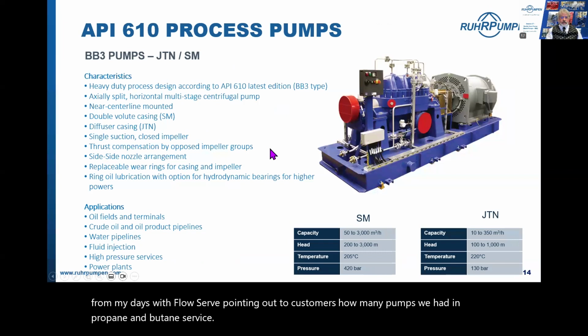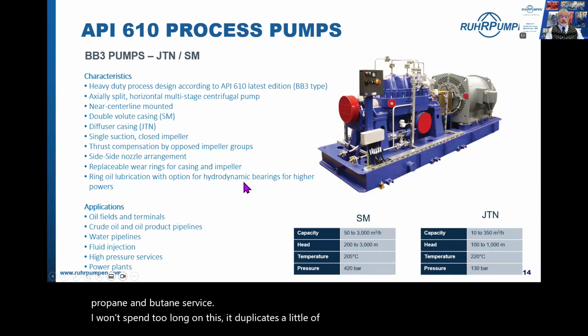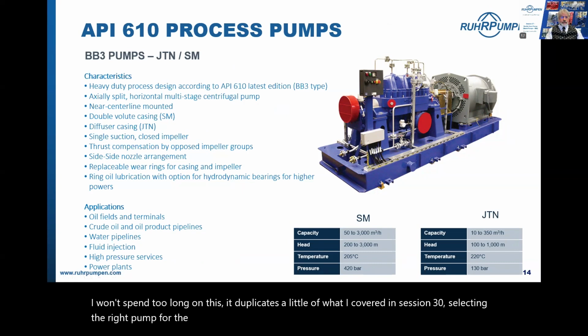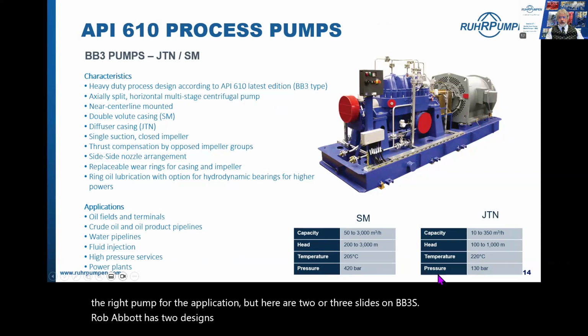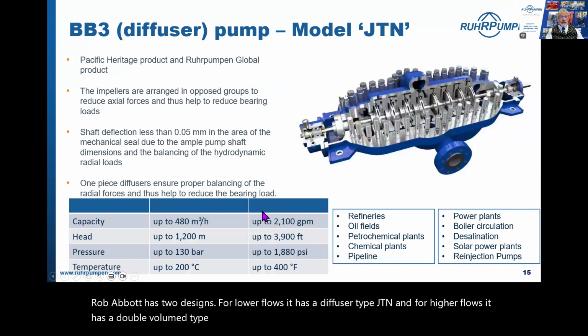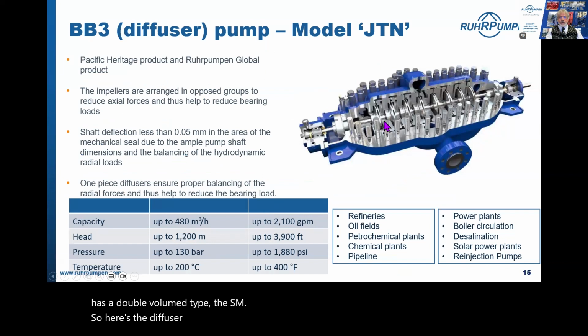I won't spend too long on this. It duplicates a little of what I covered in session 30, selecting the right pump for the application. But here are two or three slides on BB3s. Ruhrpumpen has two designs. For lower flows, it has a diffuser type, the JTN. And for higher flows, it has a double volute type, the SM. So here's the diffuser model, the JTN. You see here the diffusers all stacked up inside the outer case.